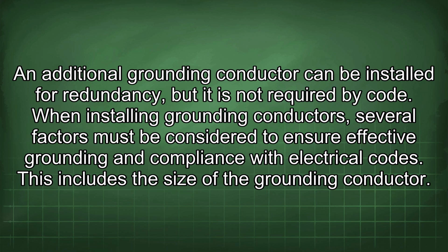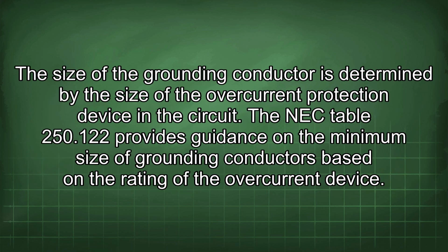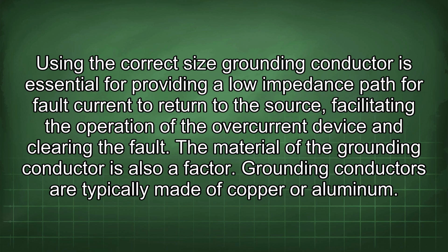When installing grounding conductors, several factors must be considered to ensure effective grounding and compliance with electrical codes. This includes the size of the grounding conductor. The size of the grounding conductor is determined by the size of the overcurrent protection device in the circuit. NEC Table 250.122 provides guidance on the minimum size of grounding conductors based on the rating of the overcurrent device. Using the correct size grounding conductor is essential for providing a low impedance path for fault current to return to the source, facilitating the operation of the overcurrent device and clearing the fault.